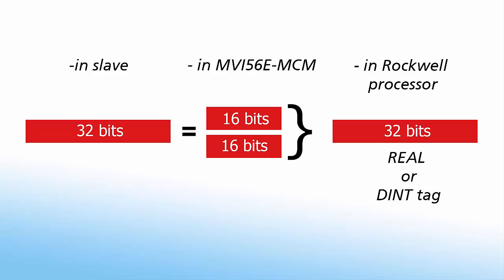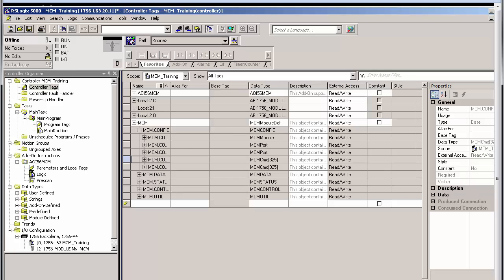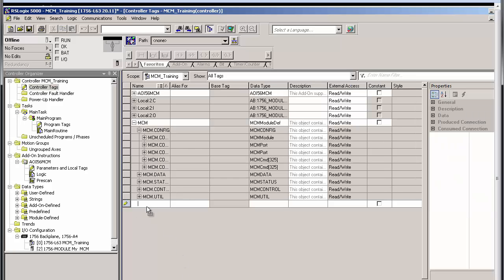That does it for the command. Now our floats will each be divided into two 16-bit words when they are read into the database. And we won't be able to view them properly unless we go through an extra step to convert them back into a 32-bit floating point number. And we'll go through that process now. So, looking at the controller tags, we'll click on the edit tab. What we need to do is create a real data array that we can copy our two pairs of words into. This will allow them to be displayed as floating point numbers.